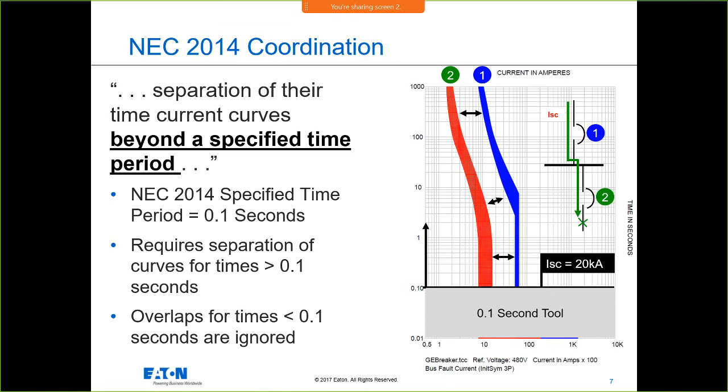And then you still have the problem, because now everybody on this phone is educated enough to know that even if I hide those, because that looks just like the BAB20 downstream of an F-150, the breaker, not the truck, right? I would know, based upon that earlier discussion, that 20,000 amps going through these two breakers is going to open both of these breakers.